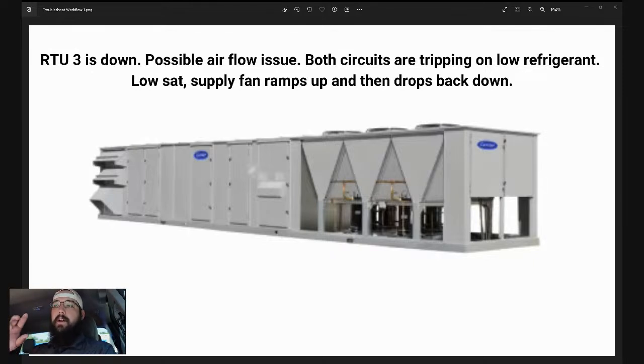A couple of feedback points that really stood out to me was, when you're doing something like this, him locking off the fan speed is perfectly fine. That is a valid troubleshooting exercise, and just putting the VFD in hand. I don't recommend running 30 hertz as your point. Obviously, we have to be mindful of our static pressure. We don't want to overshoot that pressure and end up causing any kind of damage or tripping a high static switch. But I would want to run that higher. So 40 hertz might be enough to run 2 compressors on the same circuit comfortably, but you're really probably looking at 45 to 50 hertz to get both compressors to stay on and stage together smoothly.